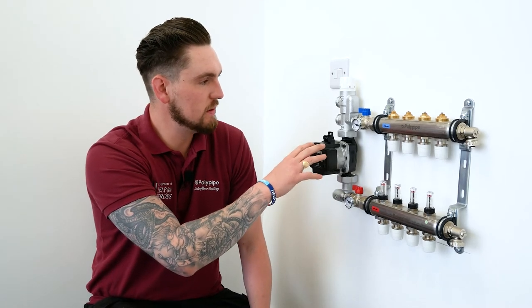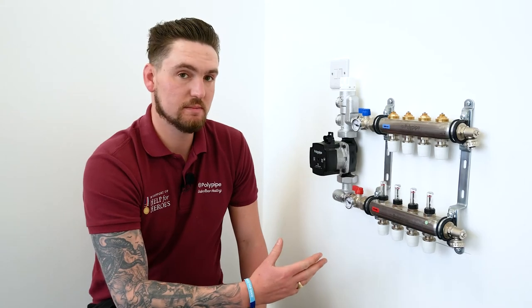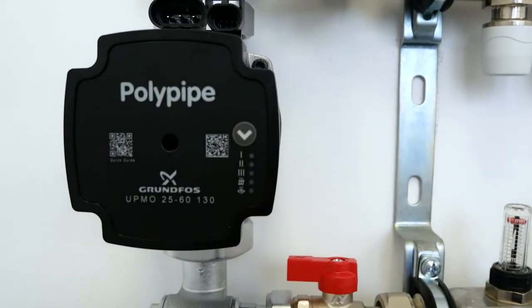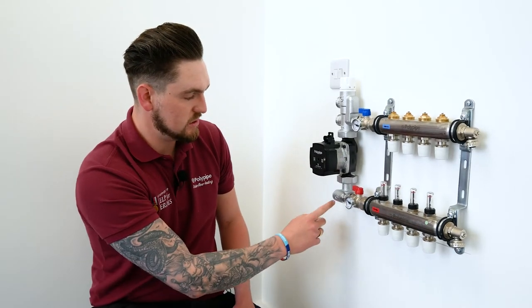First, we're going to look at the new Poly Pipe underfloor heating control pack, including the isolation valves and the auto balancing manifold. Moving from left to right, we've got the blending valve which takes a hot supply and cold supply and ensures a controlled and stable outlet temperature for the underfloor heating system. Moving down from that, we've got a Grundfos UPMO pump with the Poly Pipe branding, and at the bottom we've got an elbow. The beauty of this elbow is it enables us to quickly orientate it on the right-hand side of the manifold, due to the two unions either side making it easier to swap out and flip round.